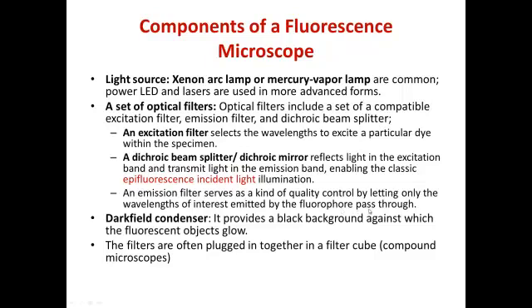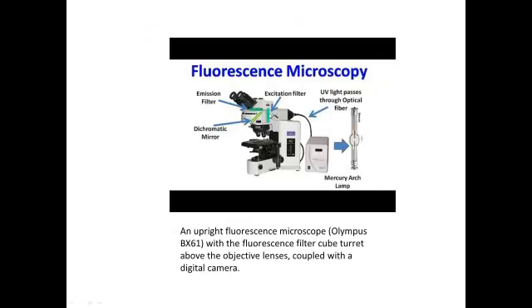Then comes the dark field condenser, which provides a black background to the image, because of which only the fluorescence is visible. Only those objects stained with the fluorescent dye will give a certain glow and can be viewed because of the particular excitation filter used. The filters are often plugged in together in a filter cube in the compound microscope, and they can be adjusted or replaced according to the requirement.